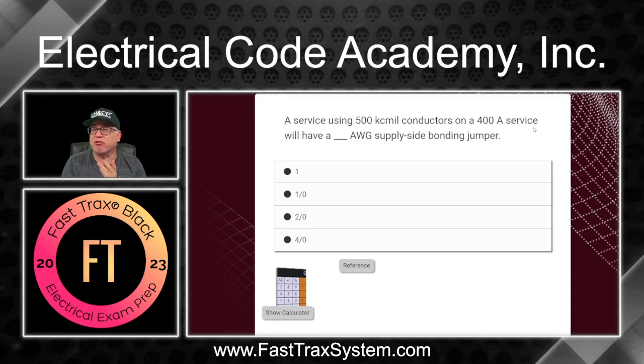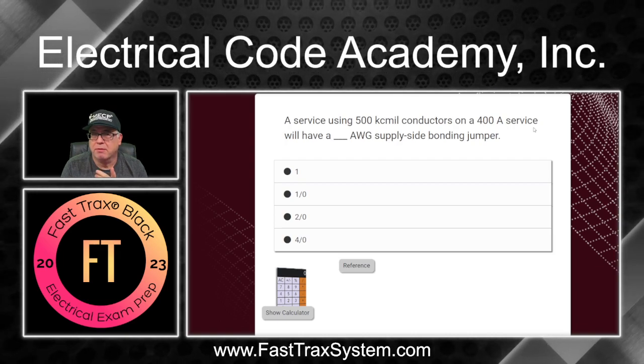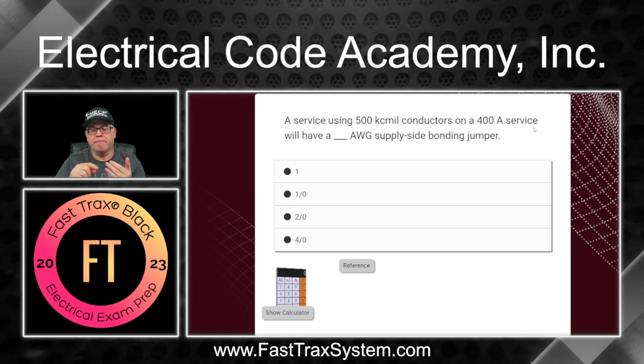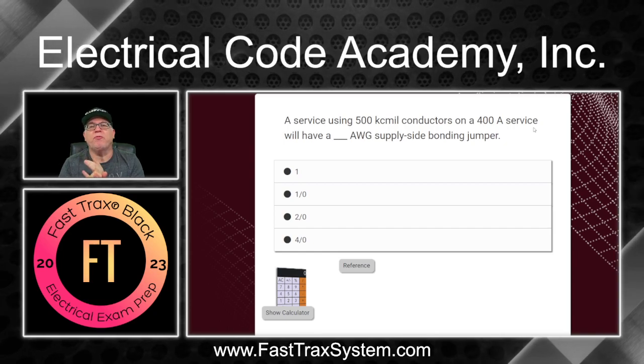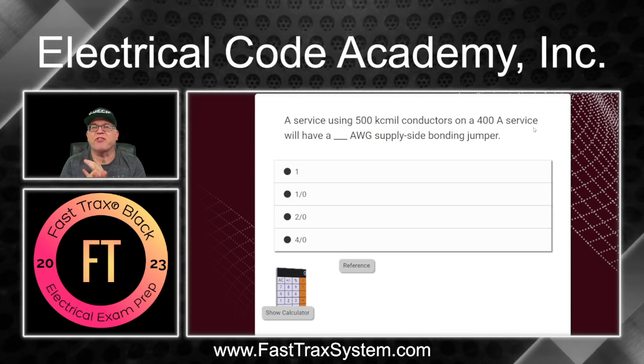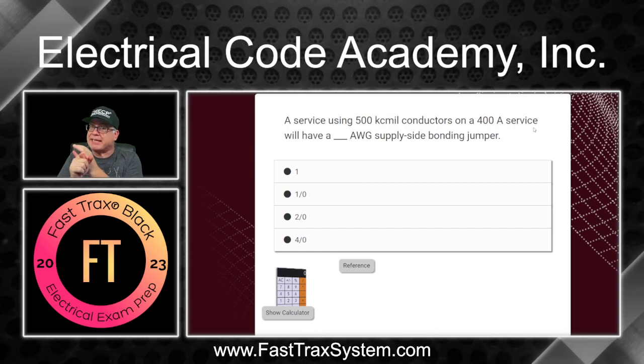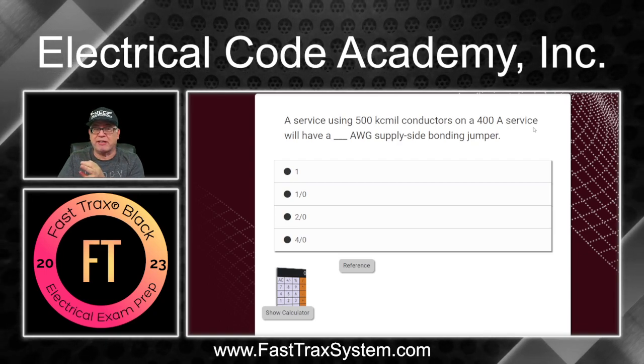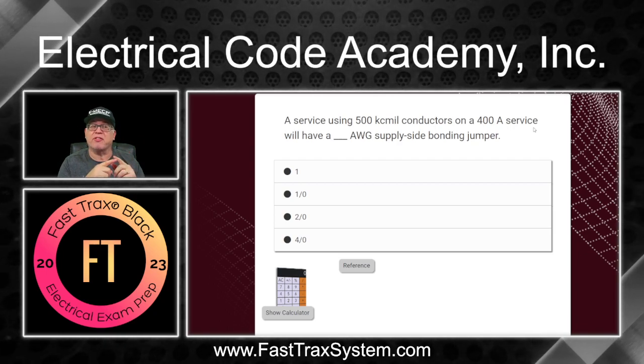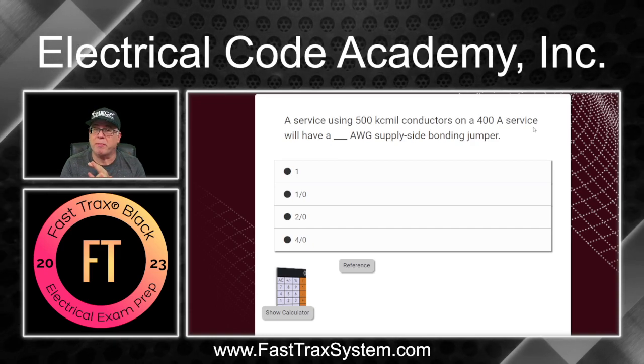250.66 for grounding electrode conductor sizing, right? Very important. 250.122 for sizing equipment grounding conductors, which go with branch circuits and feeders, based on the size of the overcurrent device. Very important to remember that one.